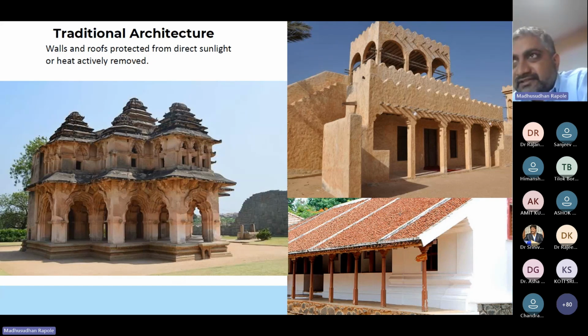What many of us forget is that what we experience is called operative temperature. If you look up operative temperature, it is some function of the air temperature and the mean radiant temperature of the surfaces you are exposed to. Because they do make a difference, and you can clearly understand this when you go into older buildings made of, say, 6 feet thick stone, or go into a cave. In a cave, or in a basement, the surface temperatures inside are not varying because of solar radiation, so what you experience is comfort, not air conditioning comfort, but natural comfort.